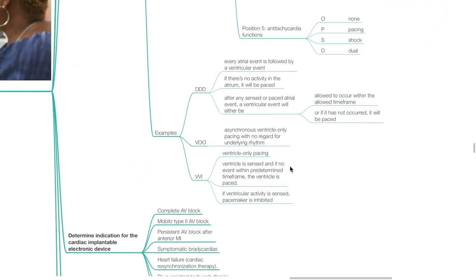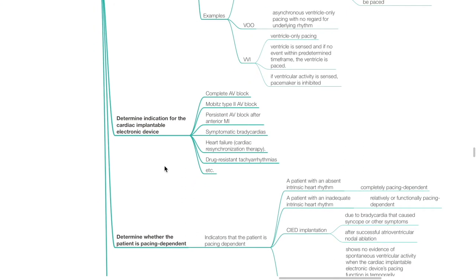Examples: DDD — every atrial event is followed by a ventricular event. If there is no activity in the atrium, it will be paced. After any sensed or paced atrial event, a ventricular event will either be allowed to occur within the allowed time frame or, if it has not occurred, it will be paced. VOO — asynchronous ventricle-only pacing with no regard for underlying rhythm. VVI — ventricle pacing only; the ventricle is sensed and if no event occurs within a predetermined time frame, the ventricle is paced; if ventricular activity is sensed, the pacemaker is inhibited.